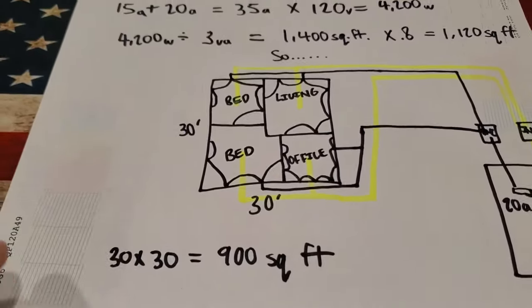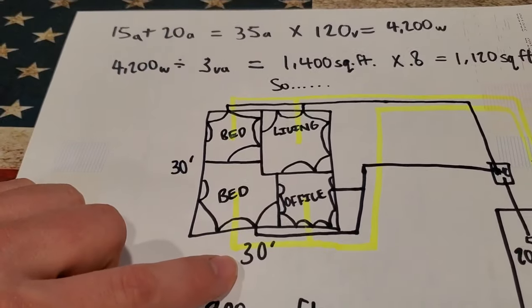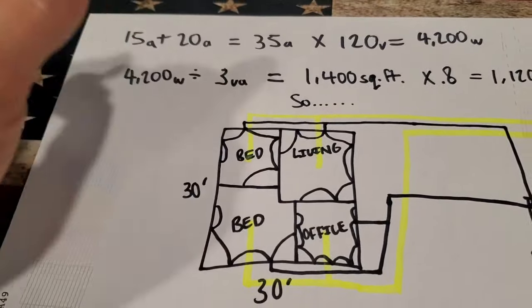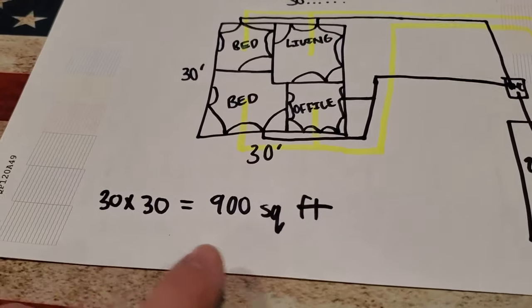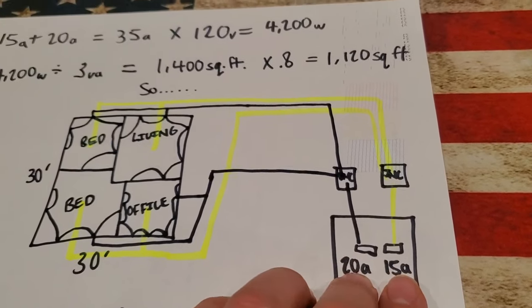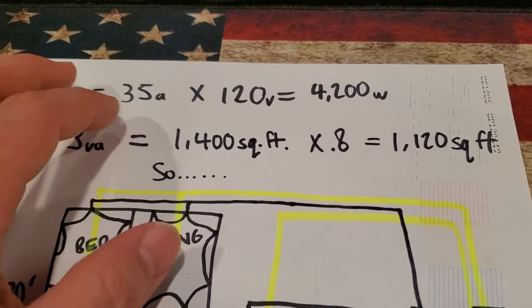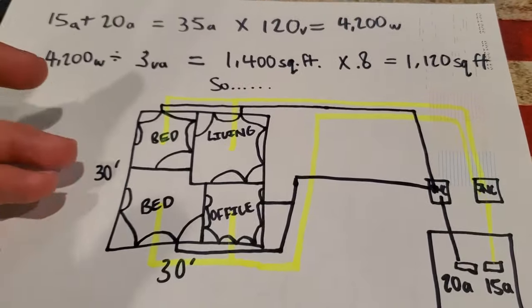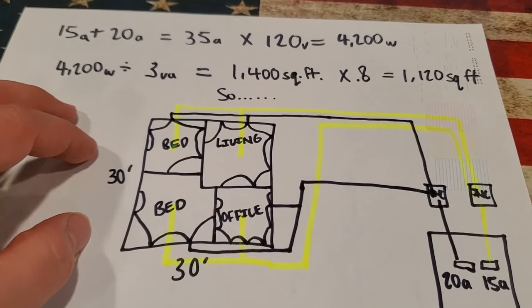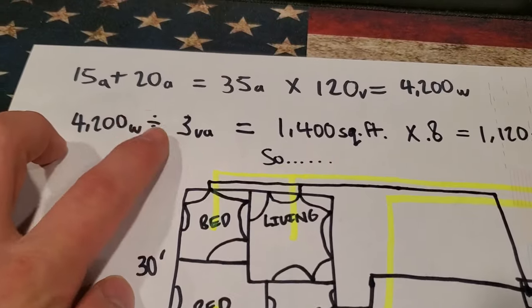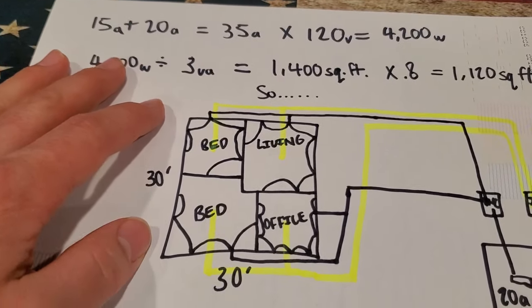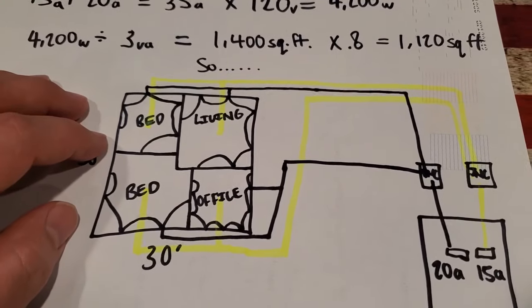Now we're going to assume that we're putting on a 30 foot by 30 foot addition with those rooms that we talked about, the living room, two bedrooms and an office. So that comes out to be only 900 square feet. So you can see with just those two breakers, a 20 amp and a 15 amp, we have plenty of power for covering this area because our lighting and our receptacle circuits are included in that 3VA figure that we've been talking about, or that 3 watts per square foot.